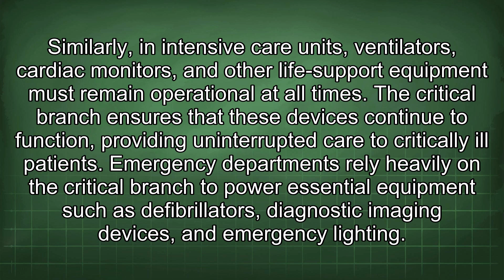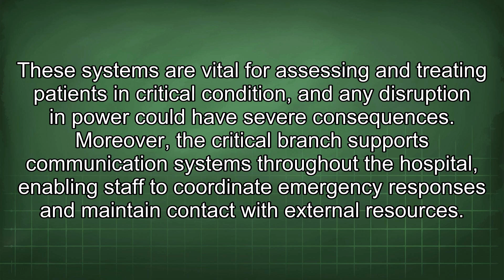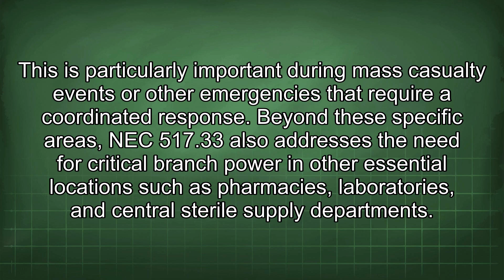Emergency departments rely heavily on the critical branch to power essential equipment such as defibrillators, diagnostic imaging devices, and emergency lighting. These systems are vital for assessing and treating patients in critical condition, and any disruption in power could have severe consequences. Moreover, the critical branch supports communication systems throughout the hospital, enabling staff to coordinate emergency responses and maintain contact with external resources. This is particularly important during mass casualty events or other emergencies that require a coordinated response. Beyond these specific areas, NEC 517.33 also addresses the need for critical branch power in other essential locations such as pharmacies, laboratories, and central sterile supply departments.